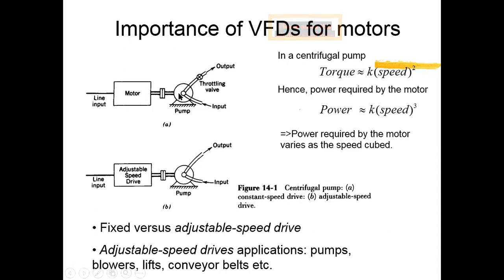Now this system is running at a constant speed, so that means all the time constant speed. But if you remove this valve and use electronics to control the motor, and use speed control, it's called VFD, variable frequency drive. When you want to reduce the flow, you reduce the speed. When you reduce the speed, the power reduces, right? It's cube. If you halve the speed, power becomes 1/8. You can reduce the power 8 times by reducing the speed 50%. You get my point, right?